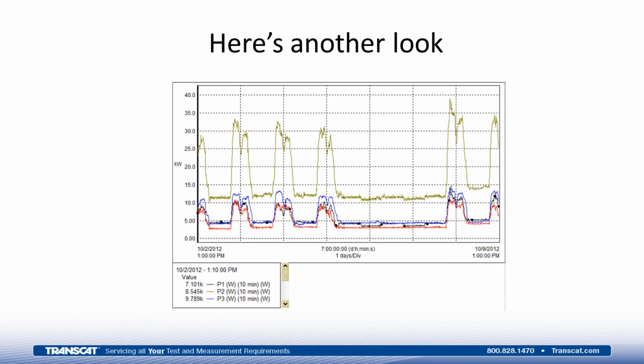What a load profile means is representing load over time. That's the term profile. From that profile, there are several things I could determine. I could determine whether or not the load is consistent, whether it's changing or fluctuating on a regular basis. I'd be able to look at the variation in that load and see how much it's varying from one side to another. That load profile could also be used in conjunction with other information. If the load profile was off of a motor running a pump, I could also look at the volume that the pump pumped and compare that to the load profile, and it would give me insight into how that motor was performing. For example, is the motor drawing way more current than it should when it's 50% or 70% loaded, which can happen on motors that are getting older. The term load profile is merely how I express energy usage over a time basis, graph it, and reuse it. Hope that answers that question, Nicole. If it doesn't, they can certainly follow up.